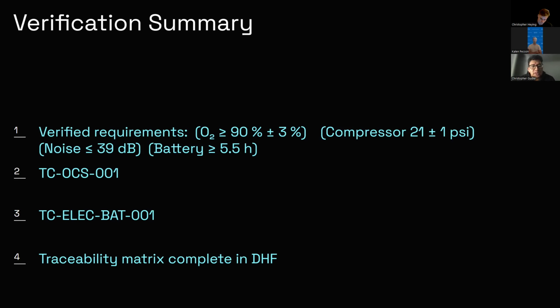The supporting test cases, TCOCS 001 for the oxygen compressor subsystem and TCELEC BAT001 for the battery system, both passed. Our traceability matrix in the DHF links every requirement to a corresponding verification result, showing complete closure for this phase. Next slide, please.